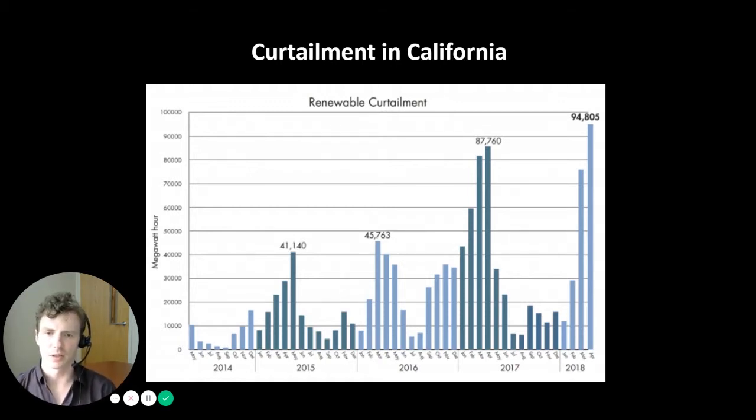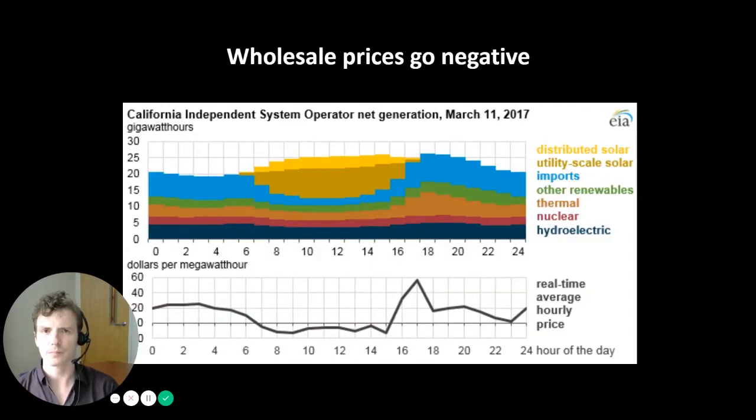And what you see is that especially during low demand periods of the year, which would be April, May, March, that also have a lot of hydropower because of water availability, and might also have a high amount of wind and solar, you're experiencing more frequent periods and more severe periods where there is just too much renewable energy on the grid in California, and increasingly some of that energy is being curtailed or forcibly turned off.